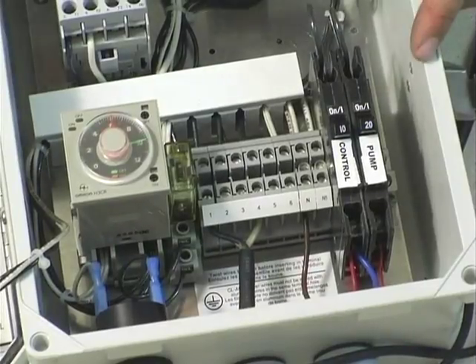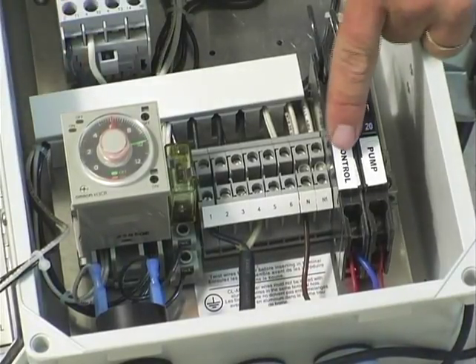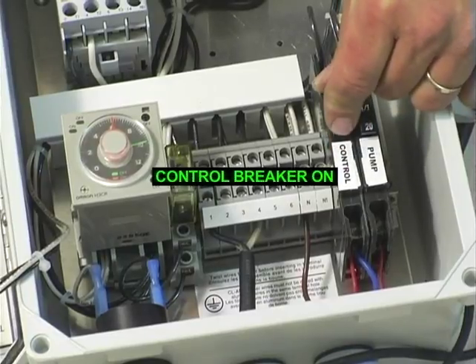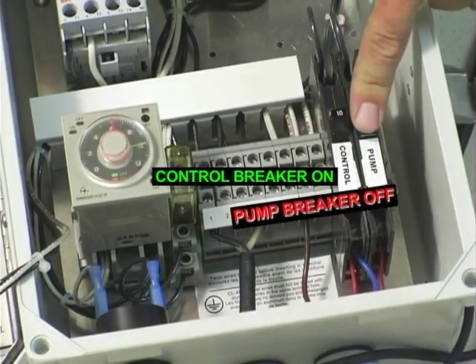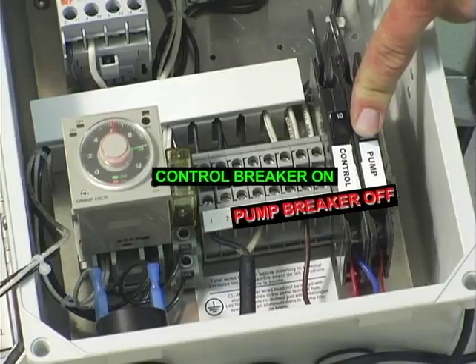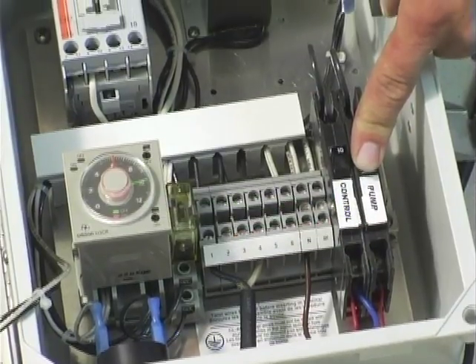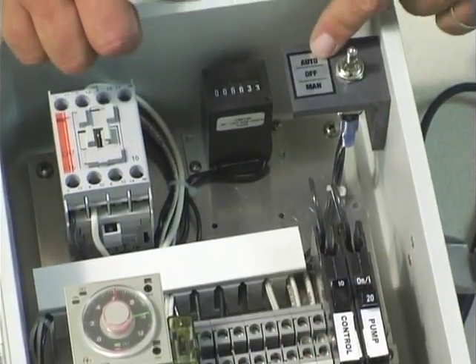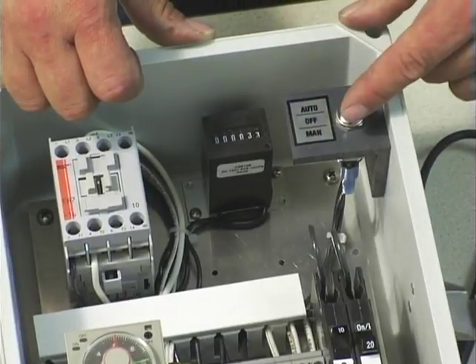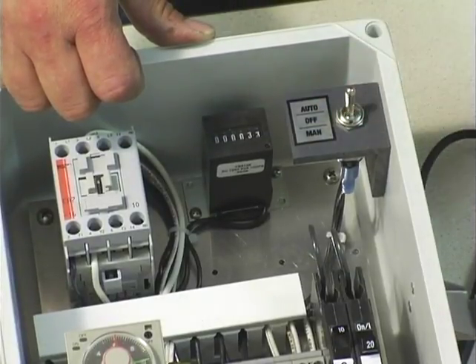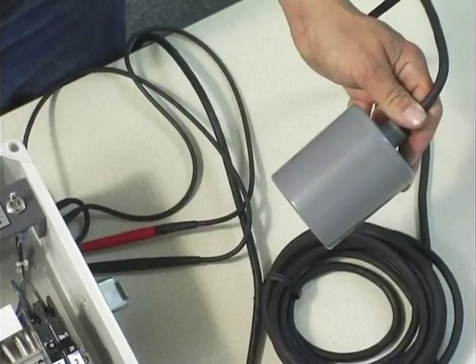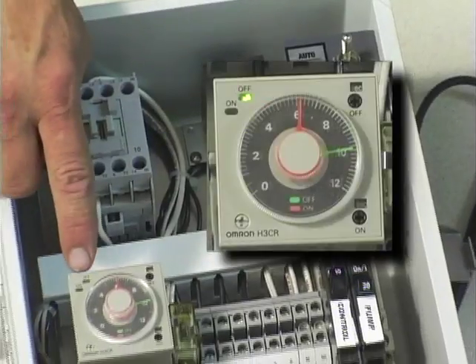What we're going to do now is test our timer. We're going to go to the control circuit breaker. We're going to turn that on. We're going to leave the pump circuit breaker turned off because we don't want to dose our pump out in the wet well while we're testing it. We're going to take our manual off auto switch. We're going to put it in auto. And now we're going to lift up our float switch, and we have a light on the timer now.